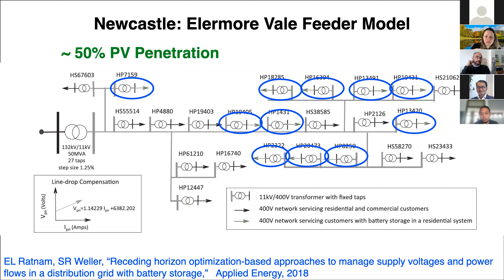That lets you smooth down the rebound peak we saw earlier. The top figure shows the case when batteries are not scheduled, where the peak load along the distribution circuit is approximately 6 megawatts. In the bottom figure, we implement receding horizon QP energy shifting, balancing customer and utility benefits, which reduces the peak load from 6 megawatts to 4 megawatts. Typically, this 2 megawatt peak load reduction is enough to defer capital expenditure on transformer capacity upgrades for many years. For example, in some rural areas, a 2 megawatt reduction could defer the need to expand a transformer costing over $1 million by approximately 10 years historically. So the batteries are doing a fantastic job.